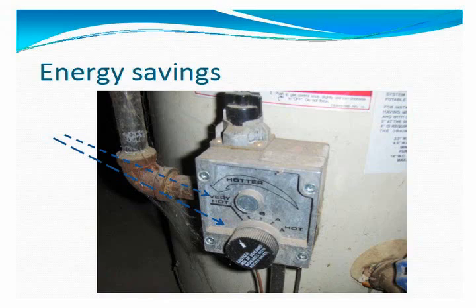Another thing we see quite often is the thermostat on tank type water heaters. Quite often the plumbers will set them to extremely hot or to the maximum setting, and the answer is simple on that. They don't want to get that call that they're not delivering enough hot water to the customer. Unfortunately, this wastes a lot of energy. You really don't get more hot water, you just get hotter water, and that takes more BTUs of energy to heat that water to this higher temperature.